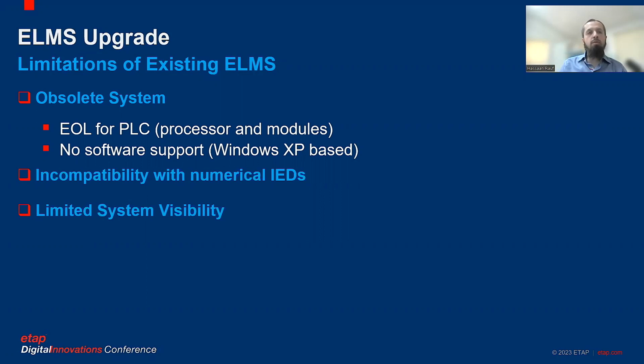On the software front, we were having the issues of limited system visibility. One of these was that we were having fixed load values for most of the loads. Due to limited real-time monitoring of the loads, most of the load values used in the PLC logic were fixed. This assumption was to some extent accurate for the motor loads, which are mostly fixed for in-plant operation, but not for the feeder loads. Again, a conservative approach was being used while having this fixed load value. So this resulted in excessive load shedding in case of any trigger becoming true.